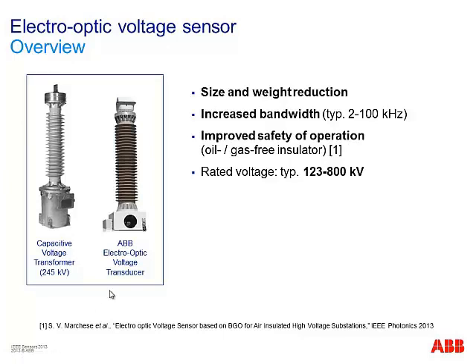Then the bandwidth can be very high for such a voltage sensor. You can easily measure up to 100 kilohertz sampling rate, which is not possible with conventional transformers. There are special transformers, but they can then not be used for normal measurements, and they are very expensive.